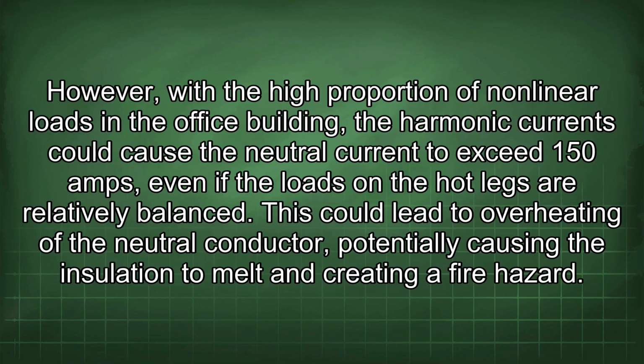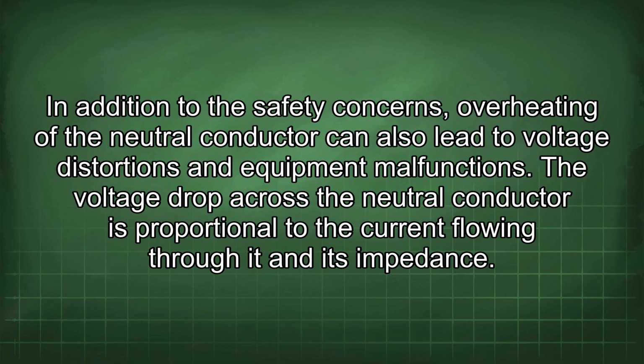However, with a high proportion of nonlinear loads in the office building, the harmonic currents could cause the neutral current to exceed 150 amps, even if the loads on the hot legs are relatively balanced. This could lead to overheating of the neutral conductor, potentially causing the insulation to melt and creating a fire hazard. In addition to the safety concerns, overheating of the neutral conductor can also lead to voltage distortions and equipment malfunctions.